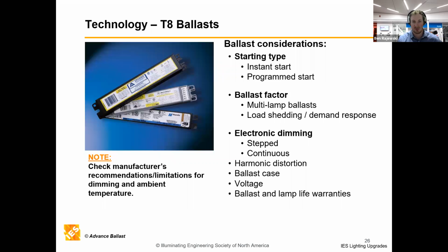When we're looking at T8s, we've got to worry about the ballasts, and when we're doing lamp replacements with LEDs, we still have to worry about the ballast, so ballasts can become an important part of that. There are different types, instant start, program start. When doing fixtures with many lamps, you needed multi-lamp ballasts and possibly more than one ballast in a fixture, depending on how many lamps you did. Dimming with fluorescents is extremely hard and expensive and not great for the lamps, so that's something LEDs have now greatly surpassed and made much easier. But you're still going to have to worry about ballasts if you're doing lamp replacements with LEDs, so keep that in mind.